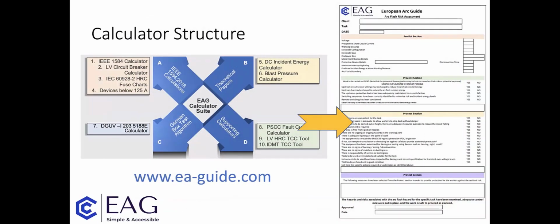But the calculator structure, what you'll find in there, if you look at the arrow on the left-hand side, A, we've got 4 calculators there that are based on the IEEE 1584 2018 calculations that I talked about earlier. There's the IEEE 1584 calculator. There's also an easy to use low voltage circuit breaker calculator, which lists out most of the devices within Europe. Then there's the IEC HRC fuse charts, what we've provided in there, and also for devices below 125 amps.